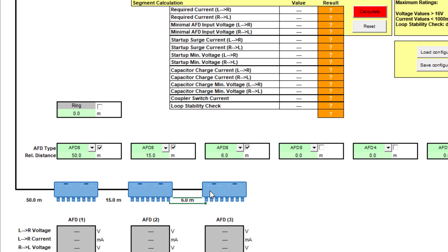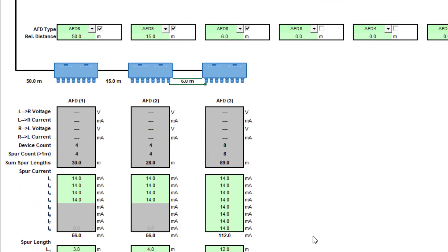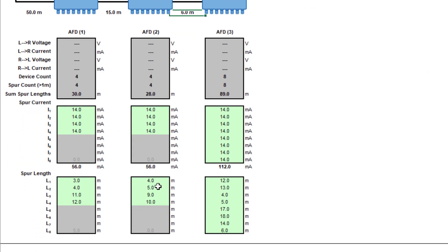I don't have to worry about the termination resistance or anything like that because the AFD will automatically terminate. What I need to do then is look at my current draw and my spur length for each of these devices.